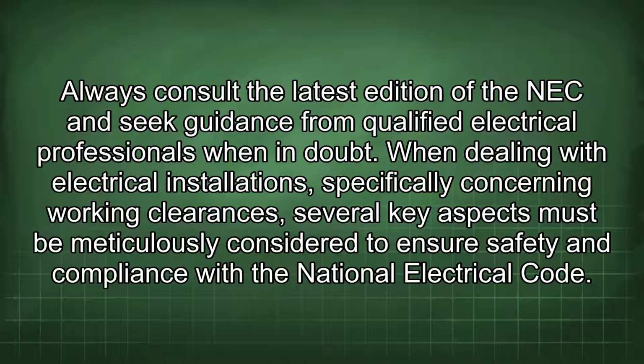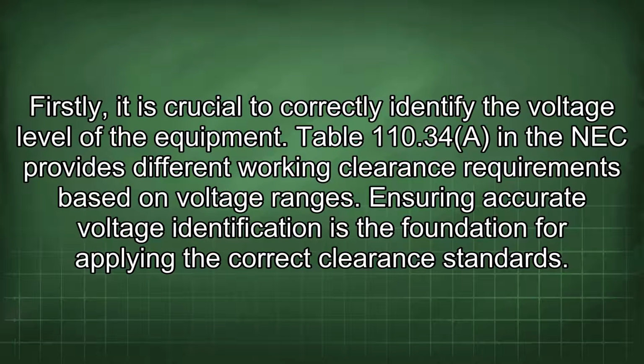When dealing with electrical installations, specifically concerning working clearances, several key aspects must be meticulously considered to ensure safety and compliance with the National Electrical Code. Firstly, it is crucial to correctly identify the voltage level of the equipment. Table 110.34 in the NEC provides different working clearance requirements based on voltage ranges. Ensuring accurate voltage identification is the foundation for applying the correct clearance standards.